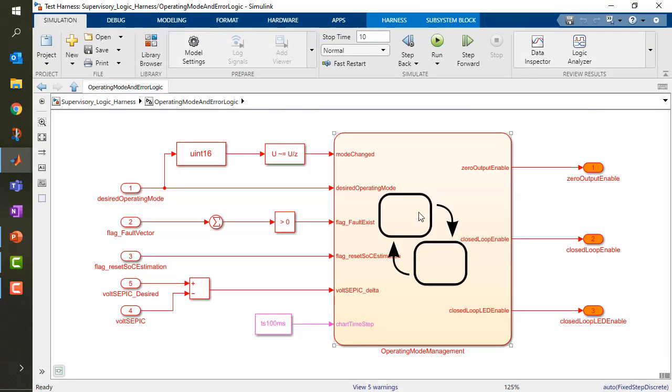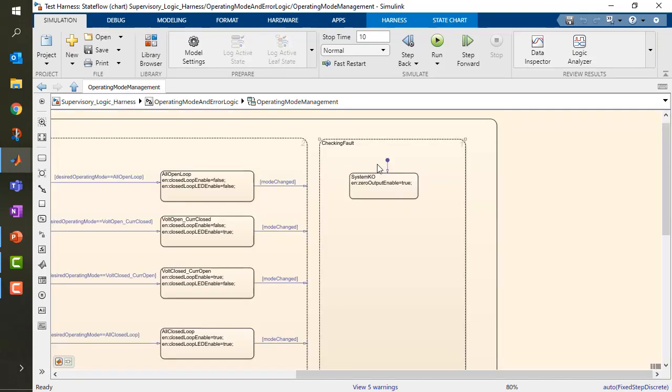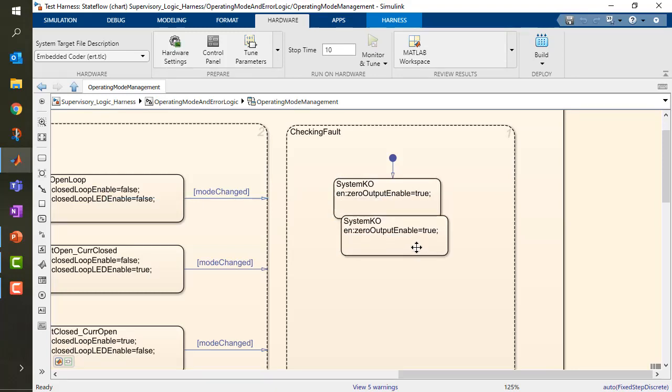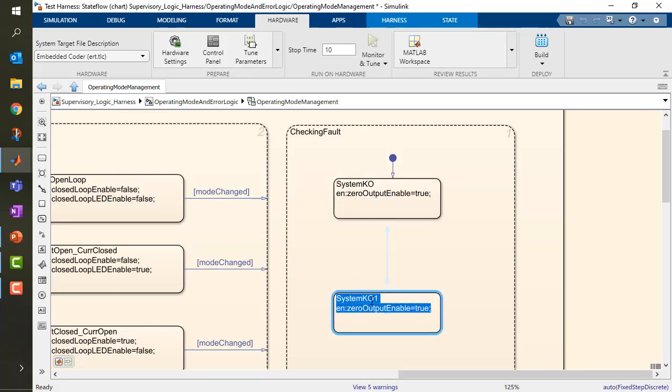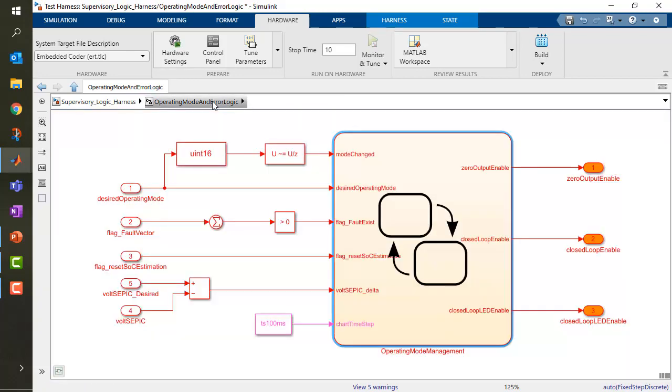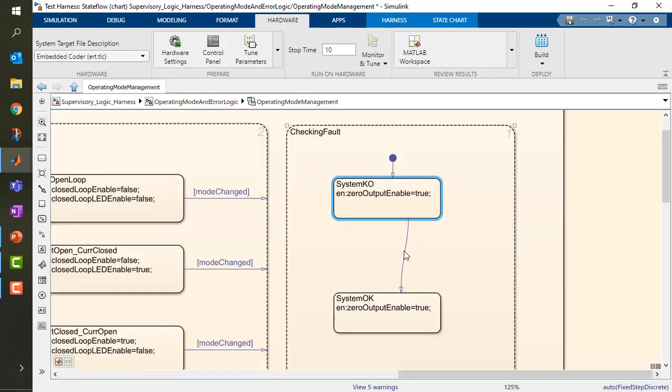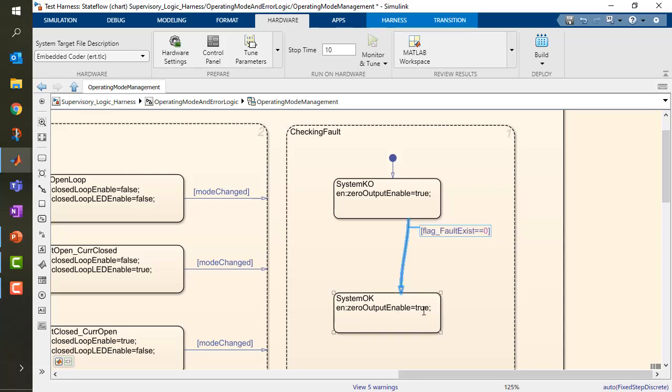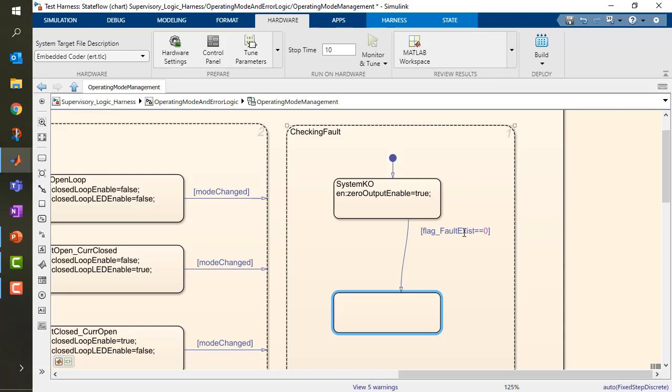Let's go within my operating logic. I see that actually, my checking fault is always true and it's never going to false. This happens because I don't have an actual something that tells me to have a system which is okay. So I add now the transition when I should go to okay. Well, I should go to okay when my flag fault exists is zero. So there is no fault. Here I'm writing flag fault exists should be zero. Then I have a system which enables my output. And this enables the zero, only zero as an output. So I would like to have something else, not zero.